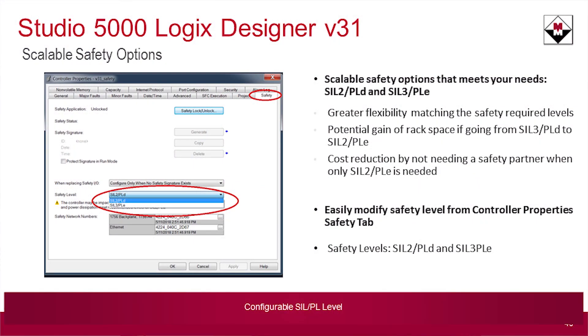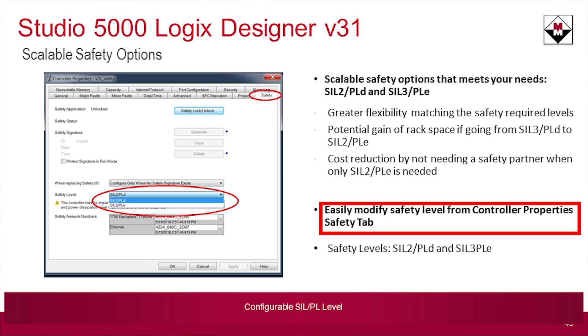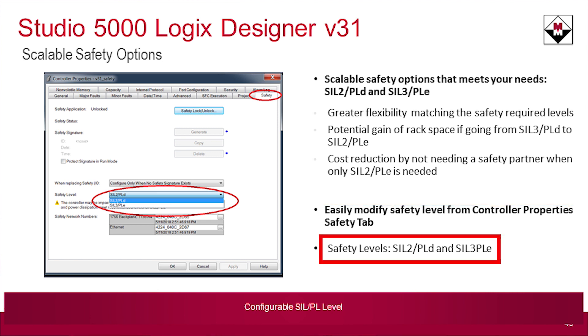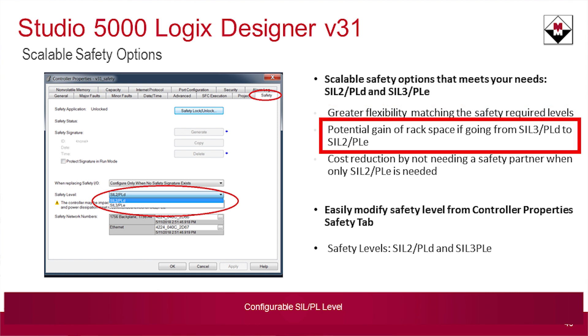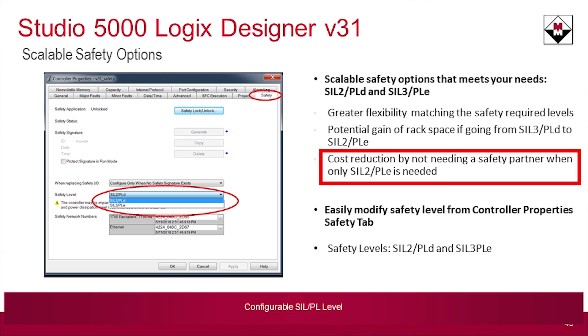The final feature I'm going to touch on is scalable safety. In the past, the hardware had to support a SIL 3 application even if you only had a SIL 2 application. Now you can select within the controller properties — if you're only doing a SIL 2 application, you specify SIL 2 and you don't have to have that second safety partner for a Logix-based application. That saves panel space, chassis space, as well as the cost of not having to buy that additional card.